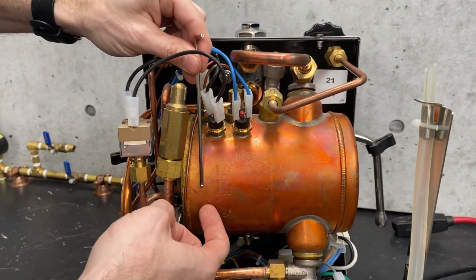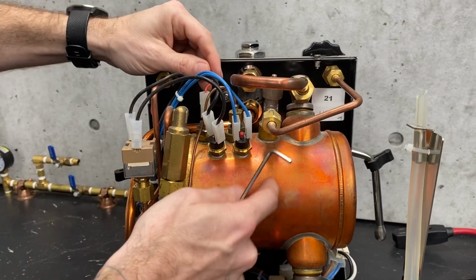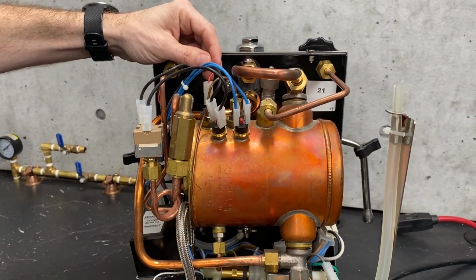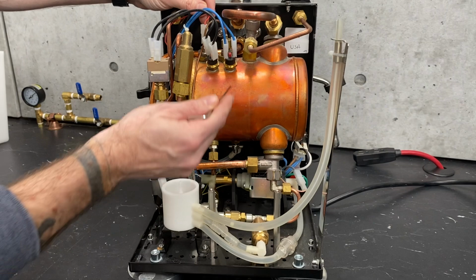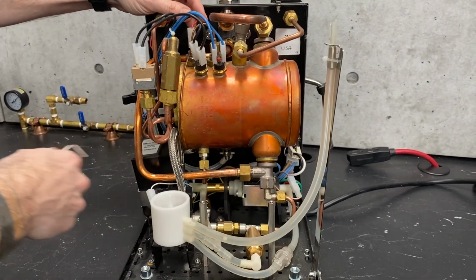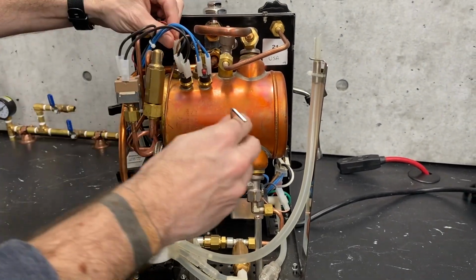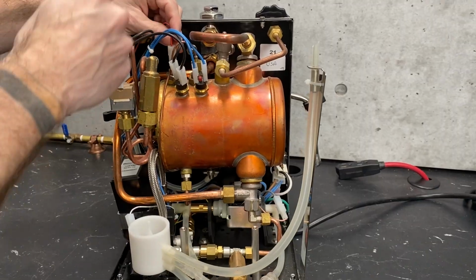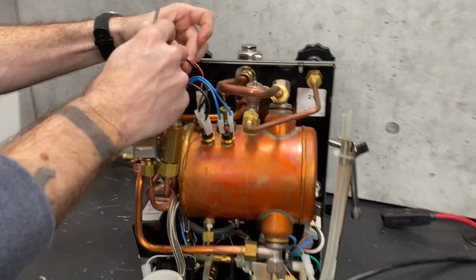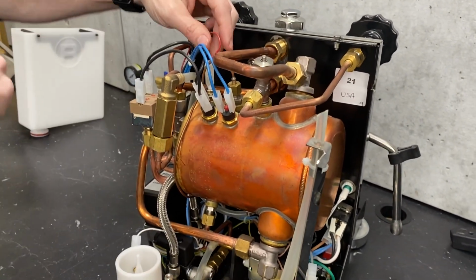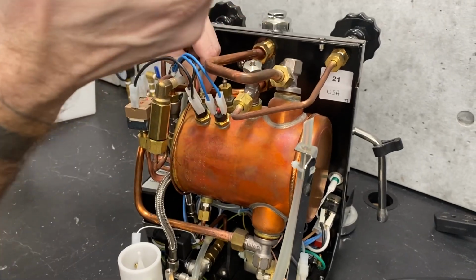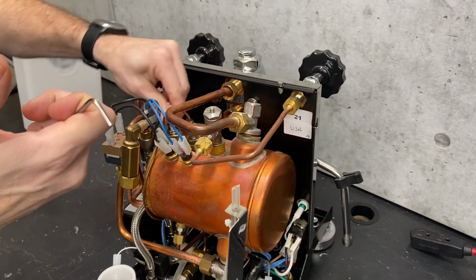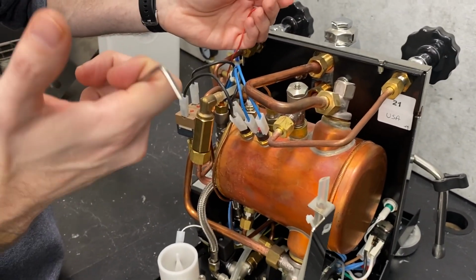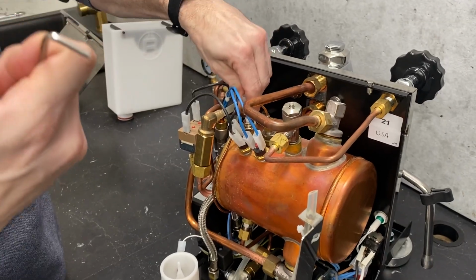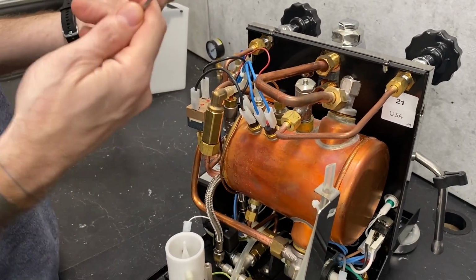It connects from there, this boiler being the ground point, so the ground wire you don't need because you have a grounded boiler. So it's its own wire. It goes through other wires to the board to communicate that, and then through this red wire down to the board. So if your boiler feels like it's not filling when it should be, you could always just pop that off, and if it starts trying to fill, then you know your liquid level control circuit is actually working right.